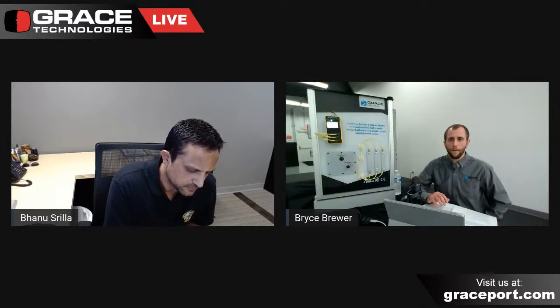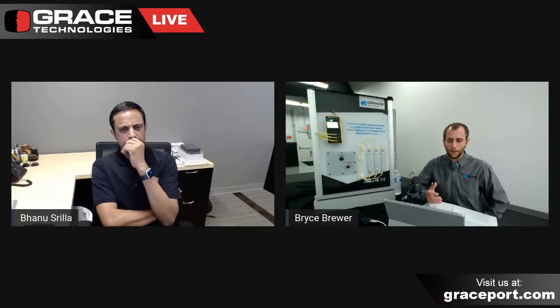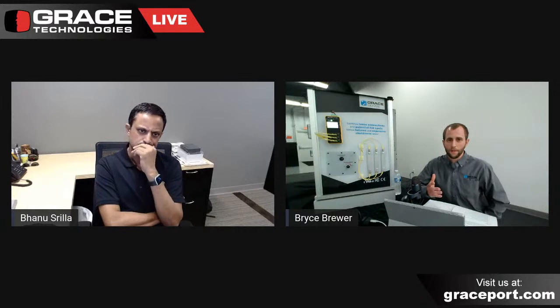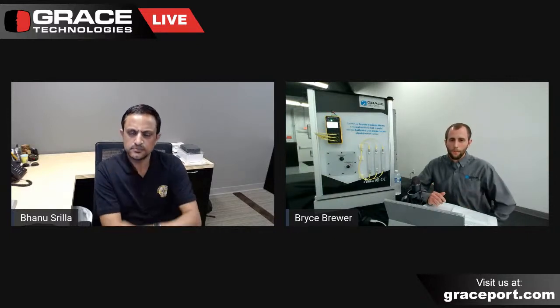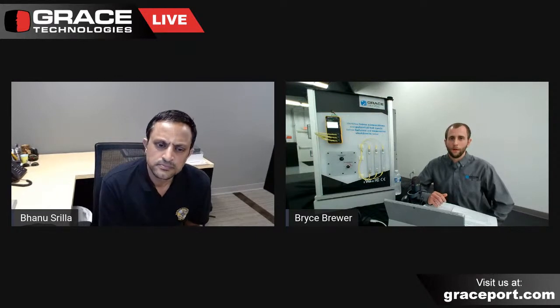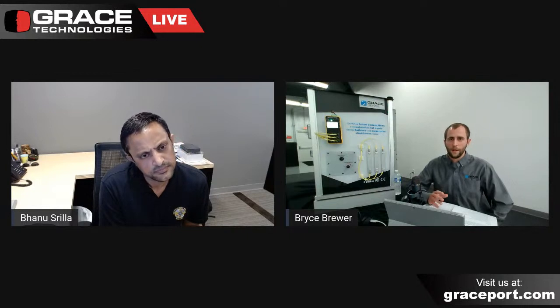I've seen technologies like a permanently mounted IR camera inside the cabinet looking at the connection. There are also your typical thermography scans done on a monthly schedule using either open door or closed door thermography. Grace was looking for a solution that was permanent but didn't have some of the failure points a camera might have, like field of view issues, keeping it clean, and being able to easily get a temperature value.